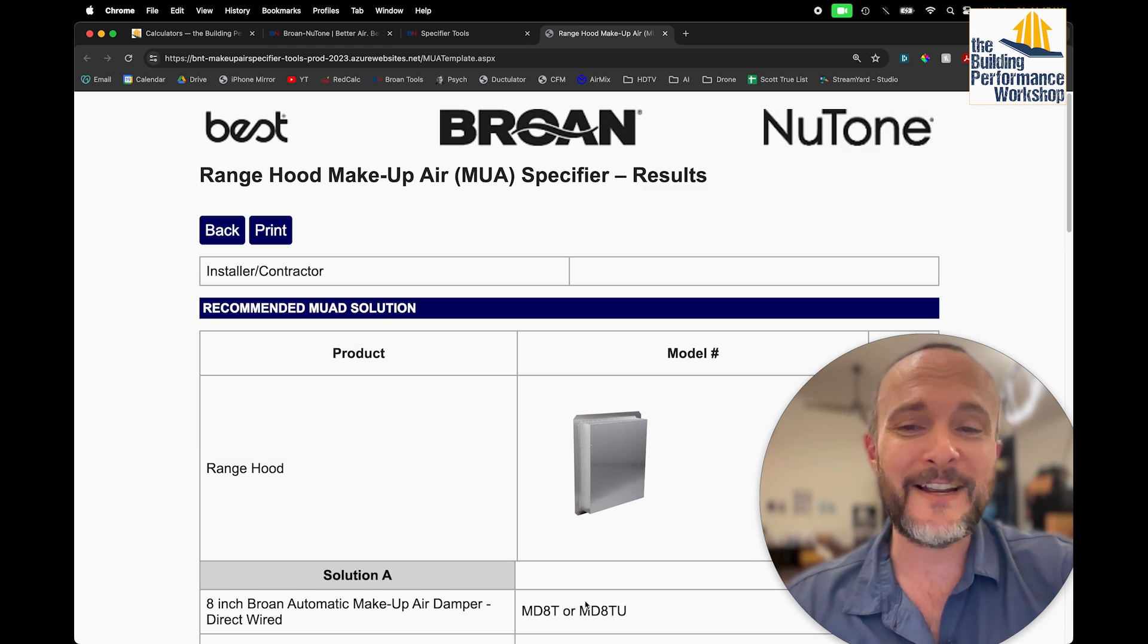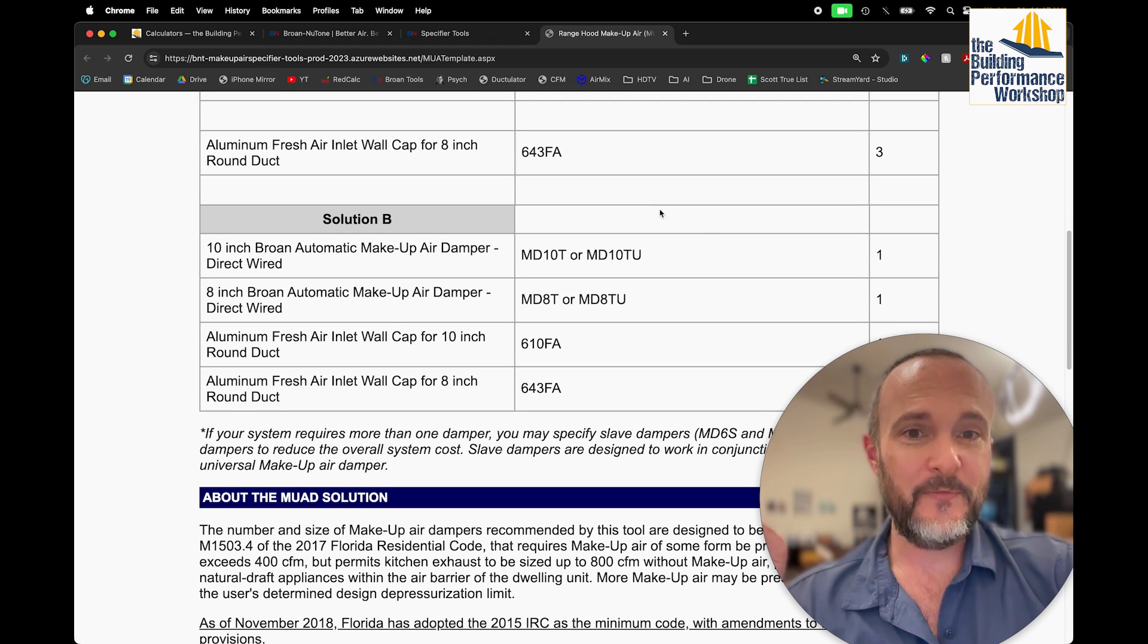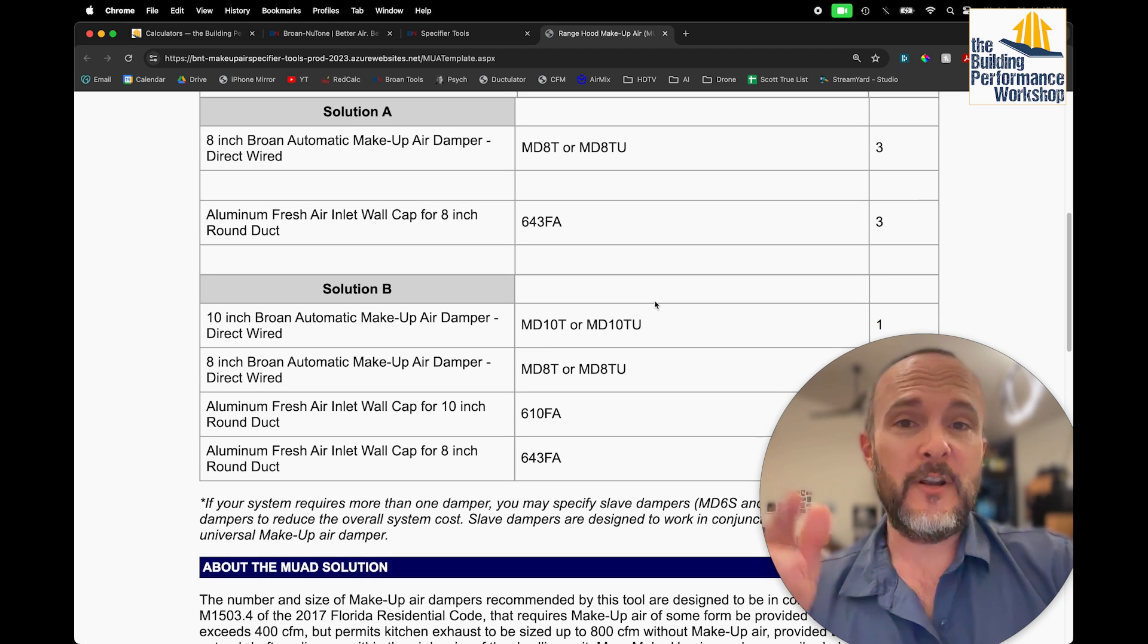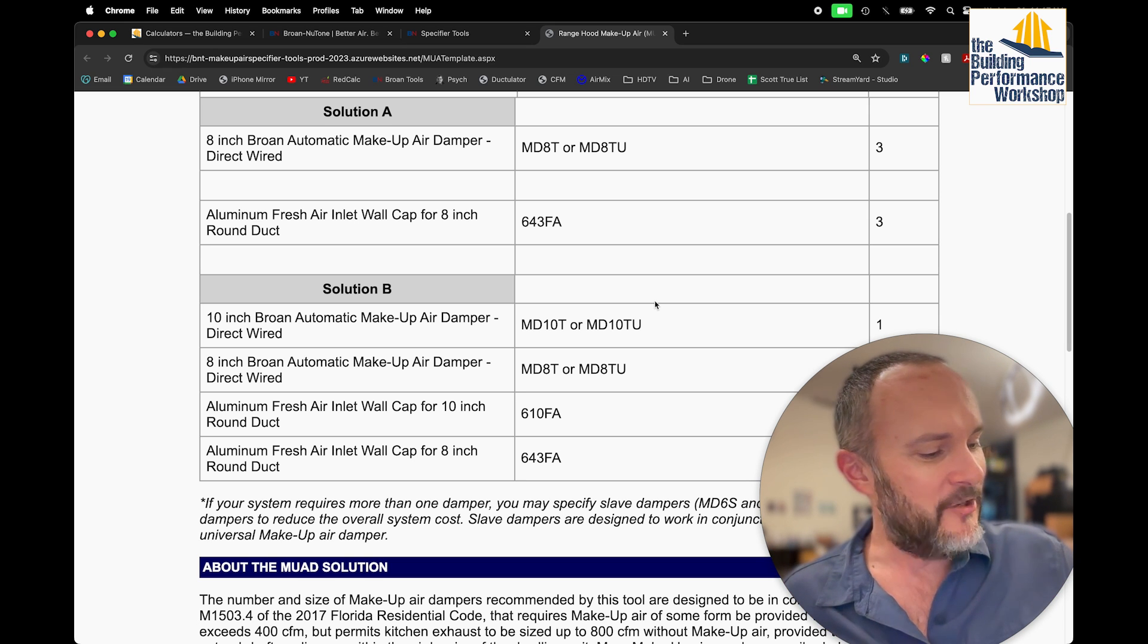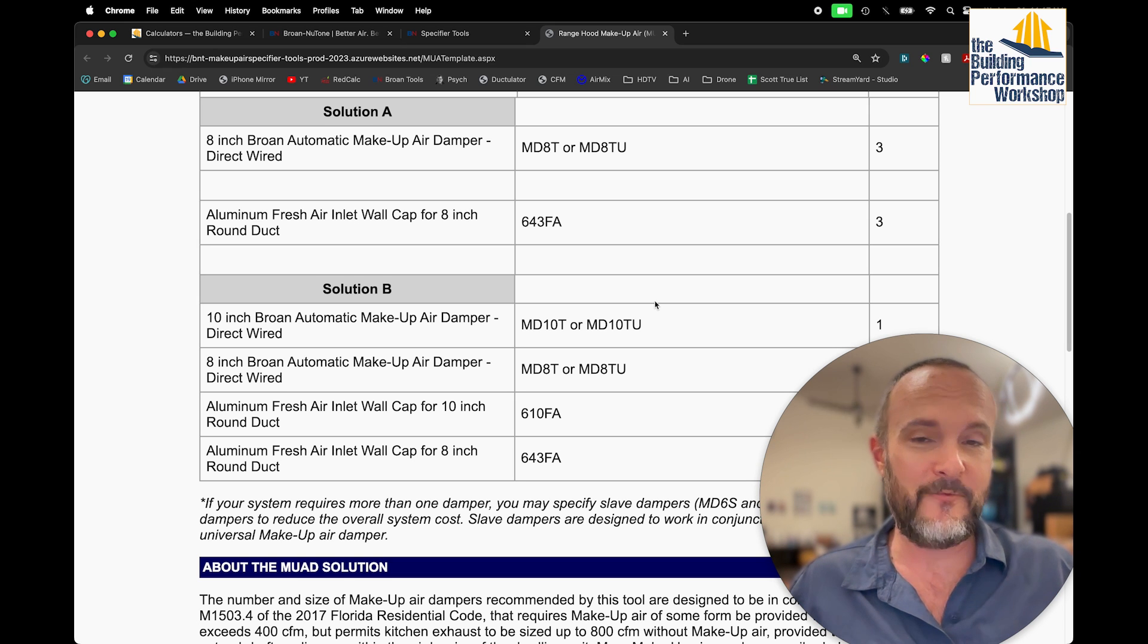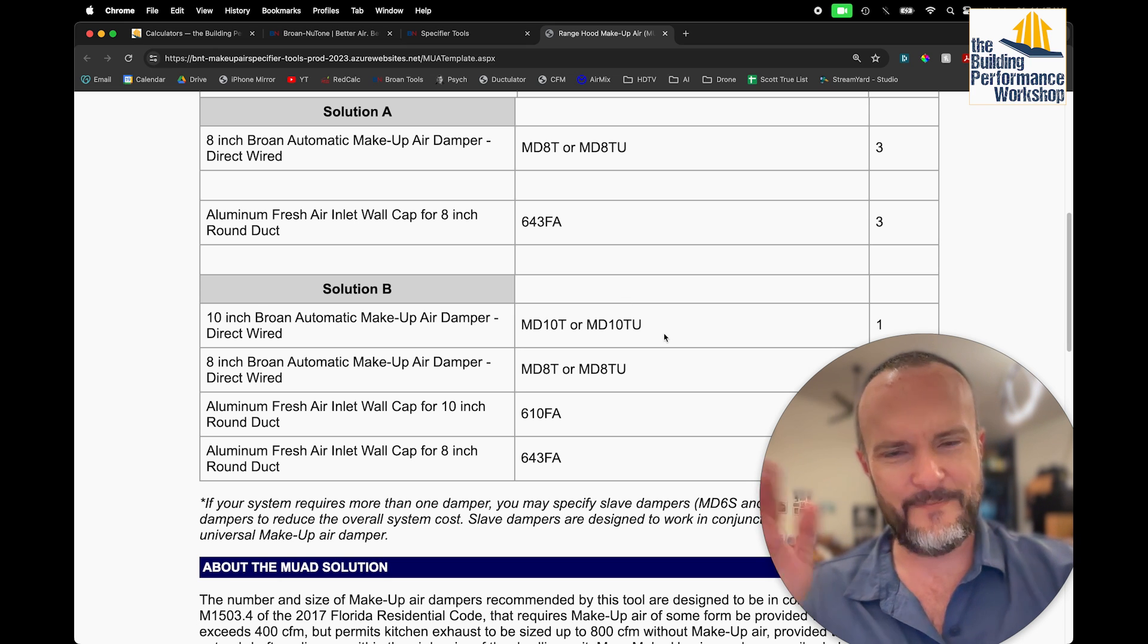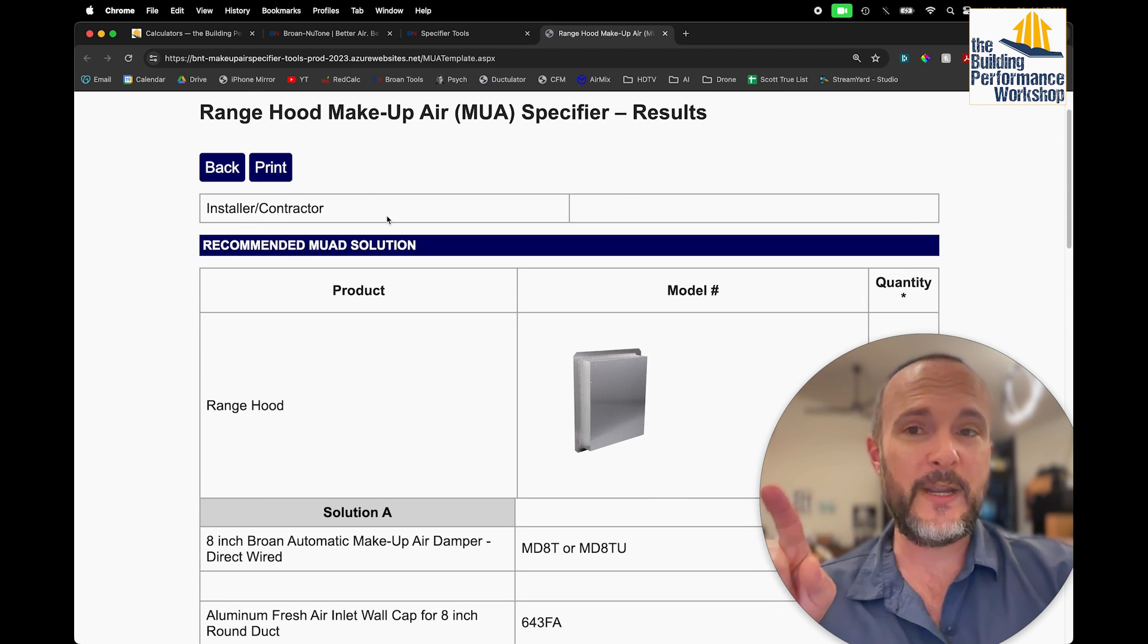Let's just do it just for the sake of argument. This is saying that in this case, we would need either three 8-inch damper ducts to outside, or one 10-inch damper duct to outside, and one 8. And we could add these together. You could find out that 8 is about 50 square inches, 10 is about 78 square inches. You take those two and you add them together, you get 128, really. You divide by pi, and then you square root that. That's going to be about a 13-inch round. If you could get a single 13-inch round damper duct, that'll also do the job for you. You're not going to find that. You'd get a 14 instead. And you can do that at, like, you can get online and go to Grainger. Broan doesn't sell one, so they're not going to tell us that we can do that. Okay. So that's what they are telling us. It's 1, 10, and 1, 8, or 3, 8.